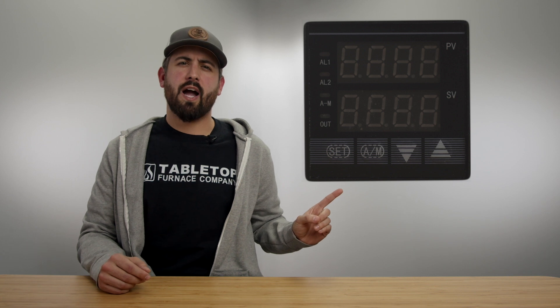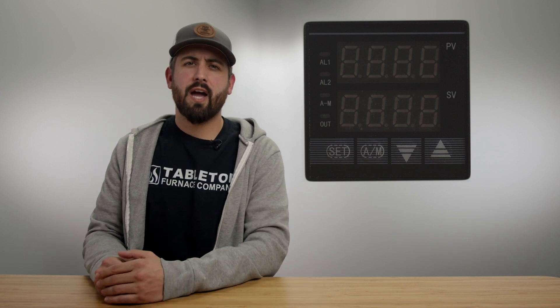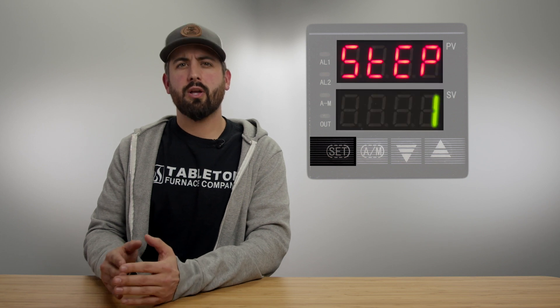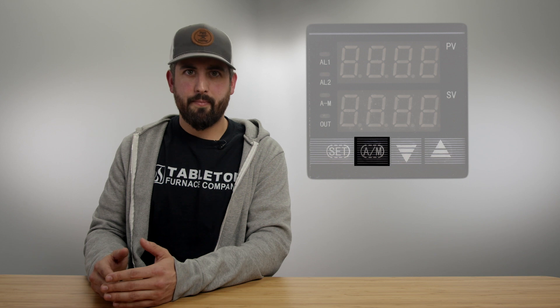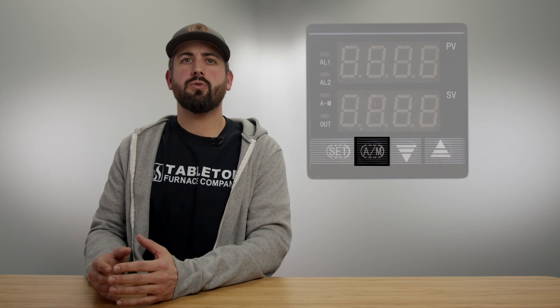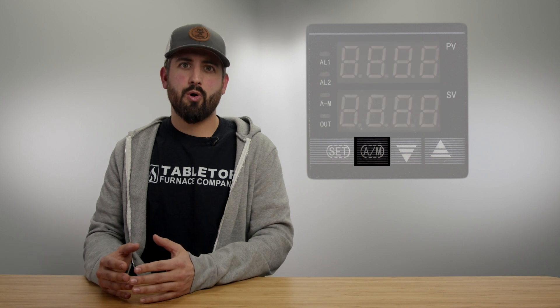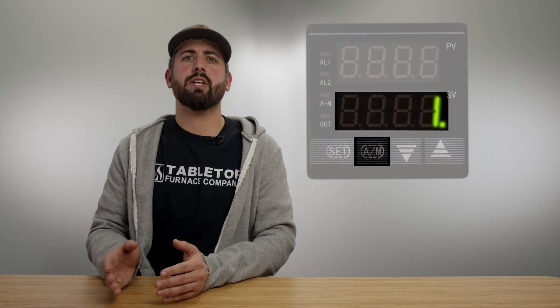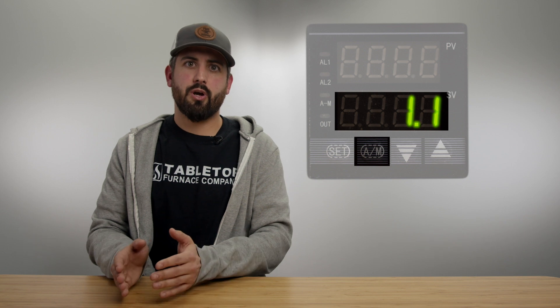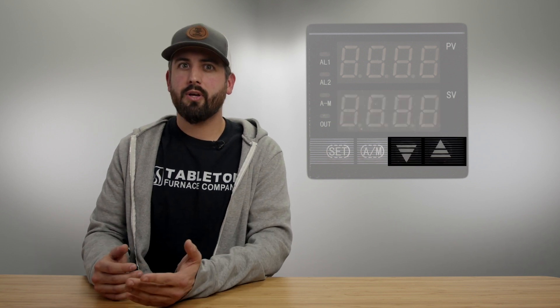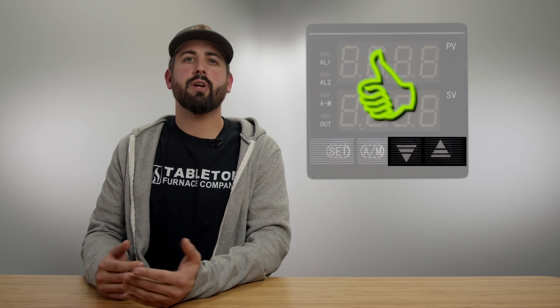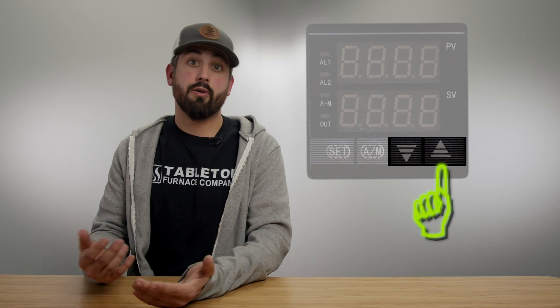Here is the digital controller you're going to find on the front of your furnace. Notice you've got four main buttons. Set - this is the button we're going to use to cycle through the different steps of a program. You've got A/M, this is going to be the button we use to start and enter a programming mode. Once in a programming mode we're also going to use this button to control the cursor to change which number we're actually going to be adjusting. Then you'll see you have an up and a down arrow. This is pretty self-explanatory. We're going to use these buttons to change your value either up or down.